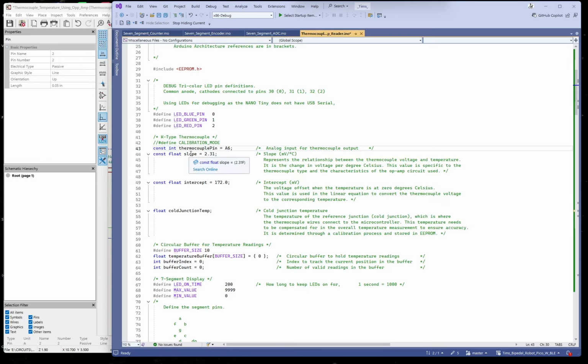So we've got another value here. We're talking about a K-type thermocouple, and the K-type thermocouple has certain characteristics. It will do certain things when certain things are applied to it, and these are known values. So the slope is how many millivolts the thermocouple puts out per degree C. You can see that it's 2.31 millivolts here per degree C. Well, that isn't what we were reading. This is more like after the op amp. But anyway, it's a value and we're using it.